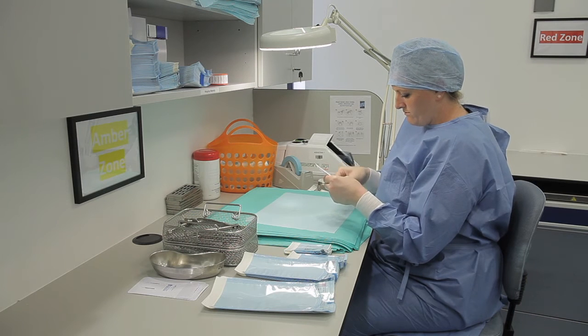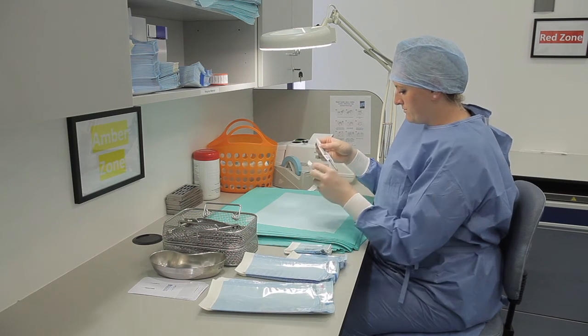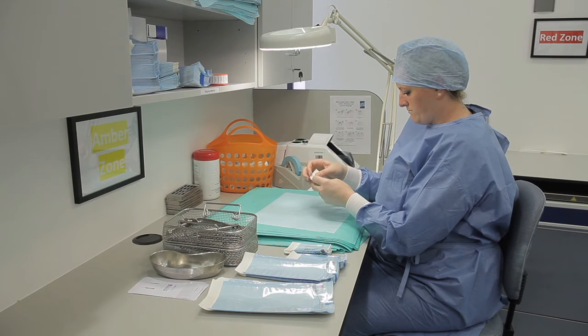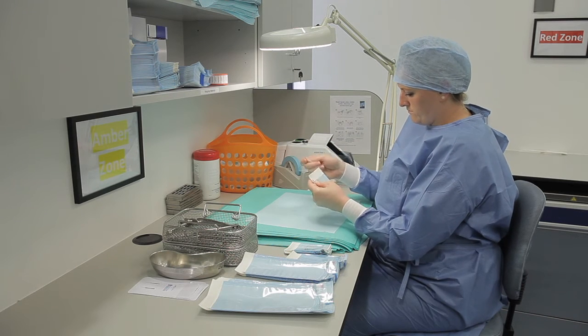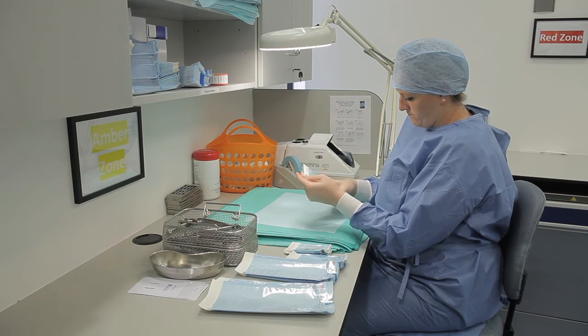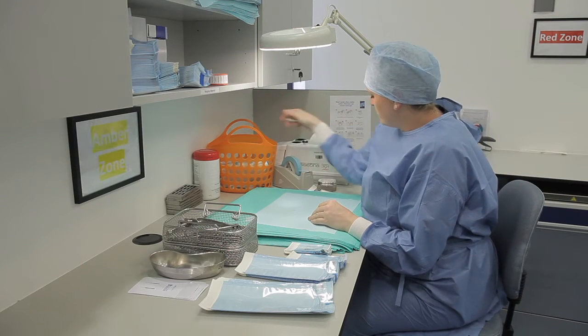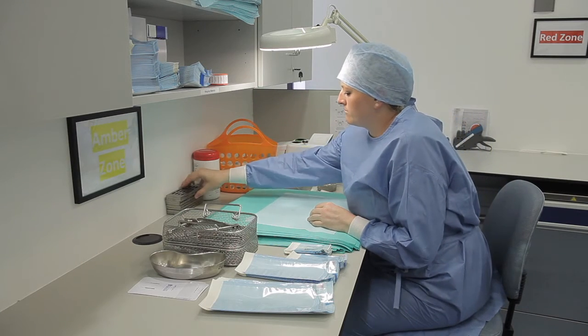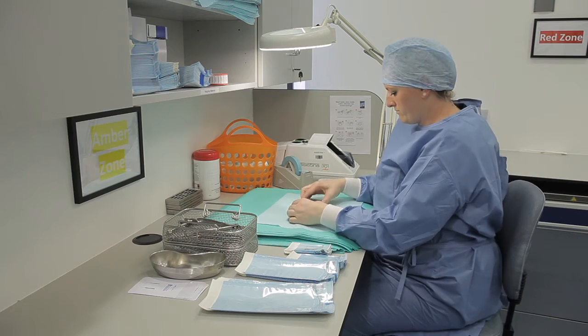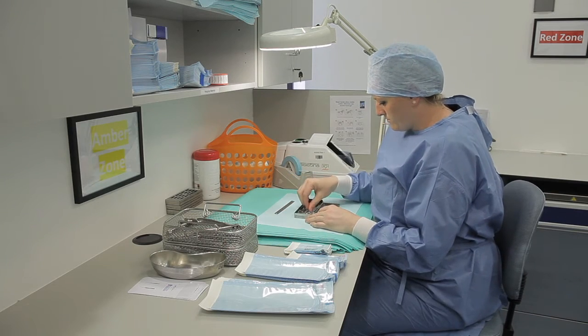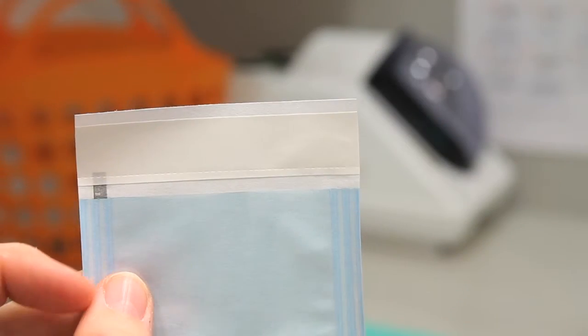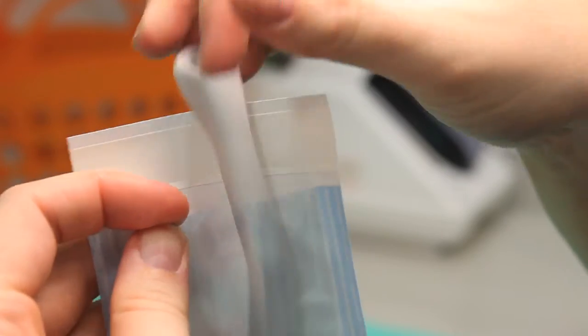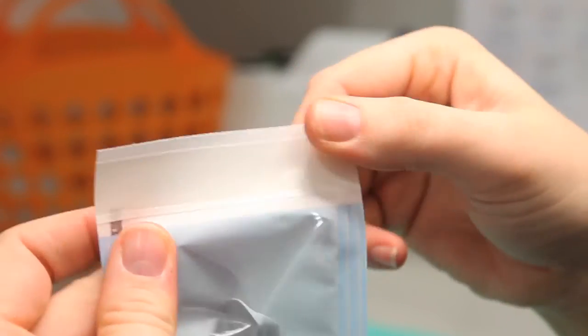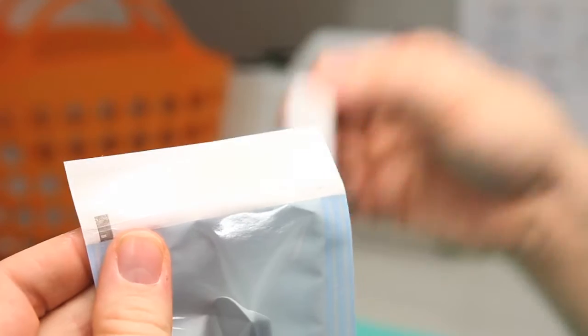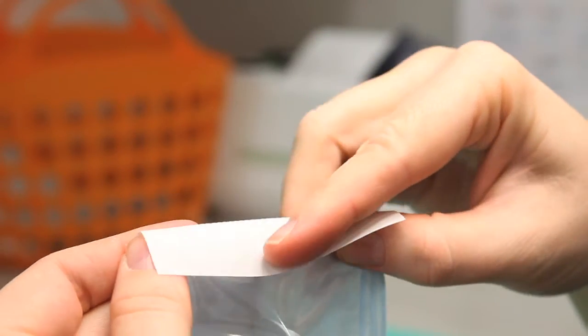When packing probes and sharp instruments, use tip protectors. This will not only permit safe handling of RIMD for staff, but also protects the sterility of the instruments by preventing puncture of the pouch. As a safety precaution, probes and sharp instruments can be double-bagged if tip protectors are not available. Each sterilisation pouch must be sealed along the perforated line to ensure that the bag is sealed correctly.